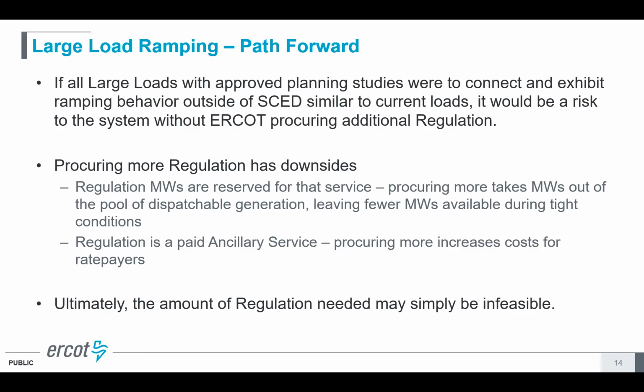It's also a paid service. ERCOT has to buy this service on behalf of consumers, so it's raising costs to buy more of it. Finally, in the same analysis linked earlier in the slide deck, we also explored what would happen if that 11.7 gigawatts of other large load that has had its planning studies approved connects to the system. What we found is that the amount of regulation that might have to be procured during some of these operating hours may just become infeasible.